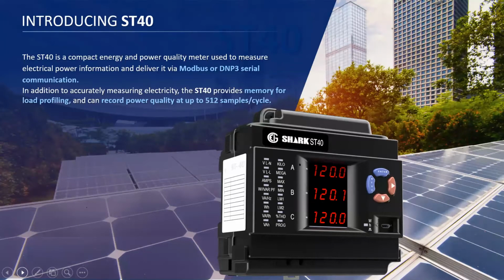In addition to the load profiling, its power quality capability is not just basic information. It will actually give you waveform captures of up to 512 samples per cycle. So even if you have really fast transients that are difficult to capture using very basic power quality, using the 512 samples per cycle, you will be able to capture waveforms for all of those fast transients and power quality issues that you may be having feeding into your line and affecting your really critical machinery.